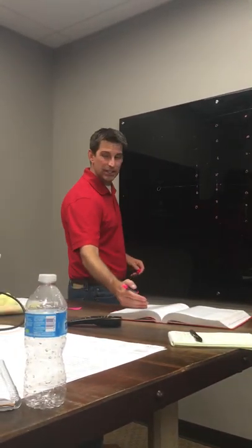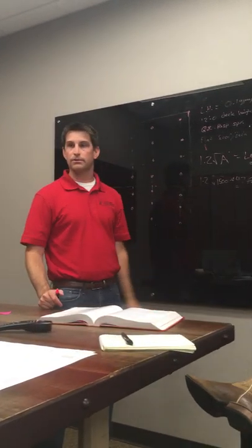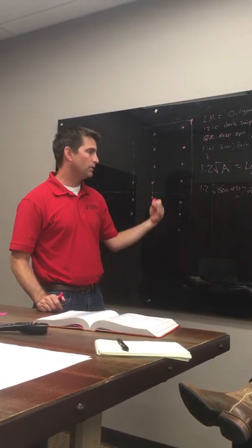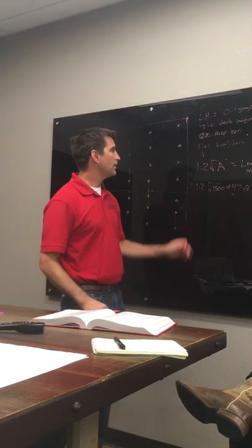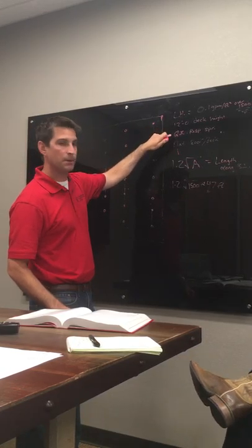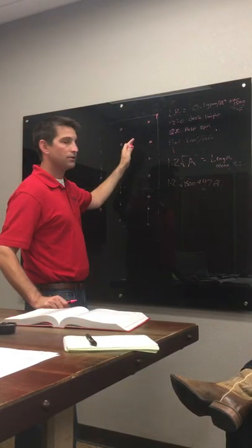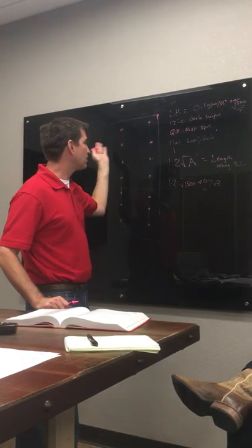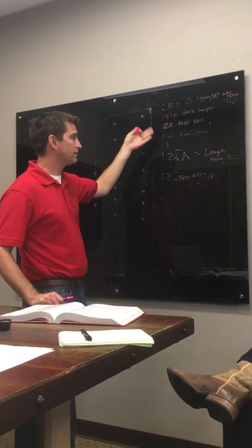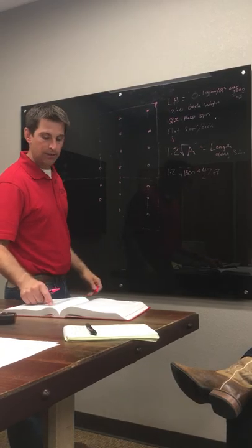Anyway, those are all the things you have to meet to be able to do the quick response reduction, but most of the time we usually meet all of them. In this case, we've got a flat ceiling, quick response sprinklers, a 12-foot deck height, under 20 feet. There are no unprotected ceiling pockets, no clouds, because it's all open, and it's light hazard, so we can do it. So now we do that equation.